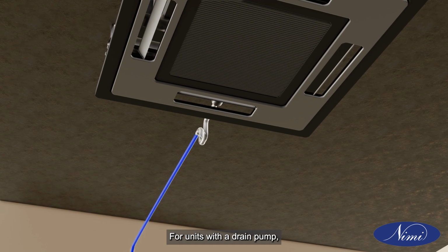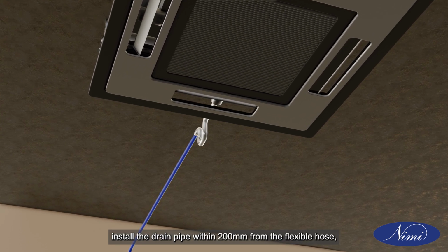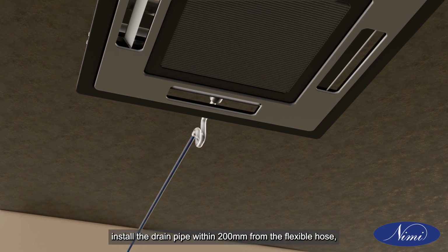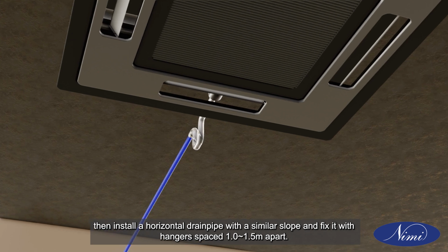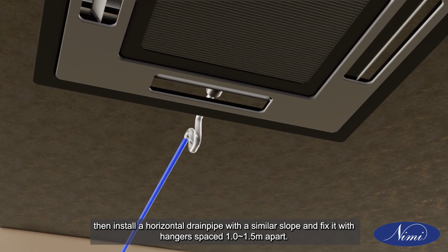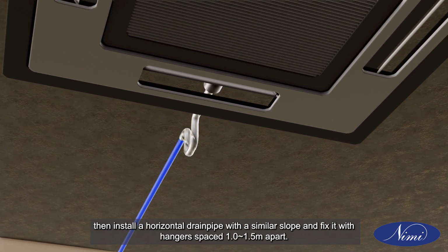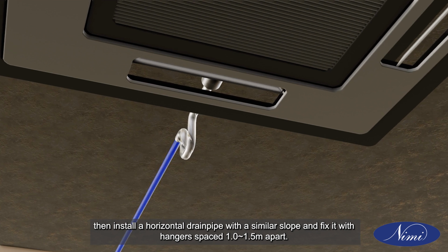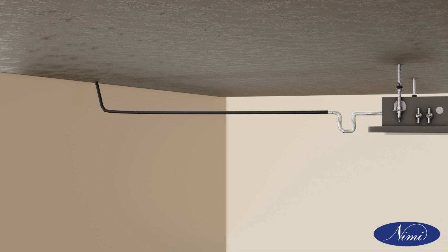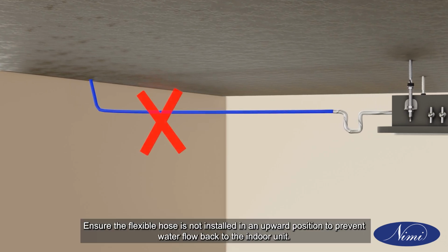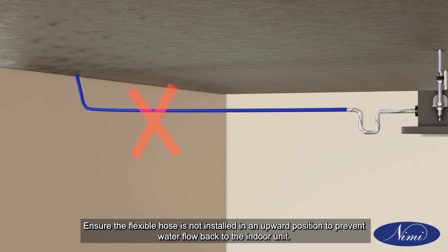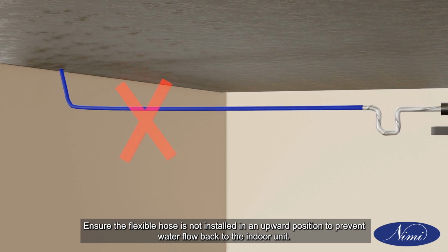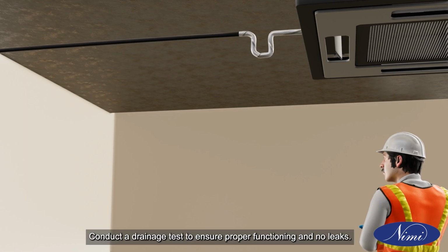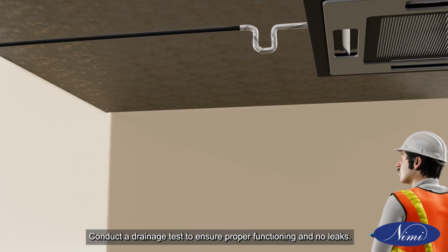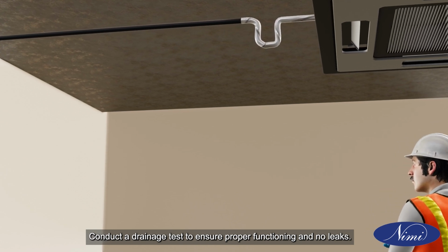For units with a drain pump, install the drain pipe within 200 mm from the flexible hose, then install a horizontal drain pipe with a similar slope and fix it with hangers spaced approximately 1.0 to 1.5 meters apart. Ensure the flexible hose is not installed in an upward position to prevent water flow back to the indoor unit. Conduct a drainage test to ensure proper functioning and no leaks.